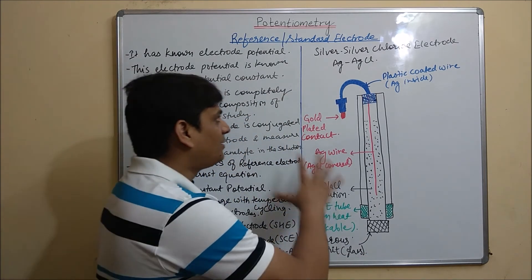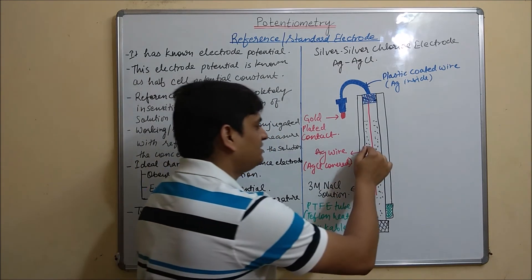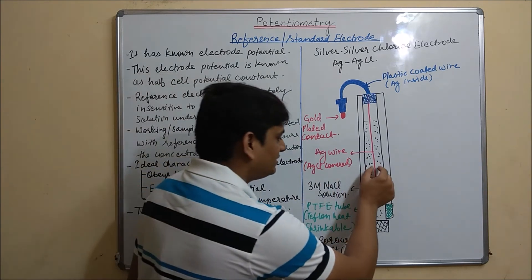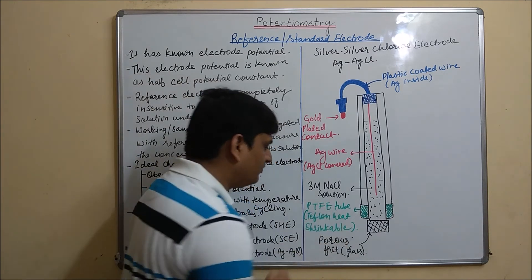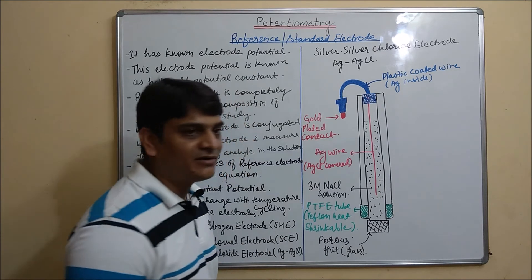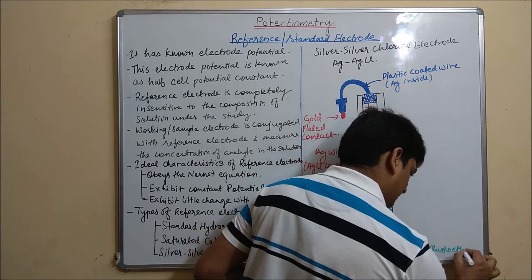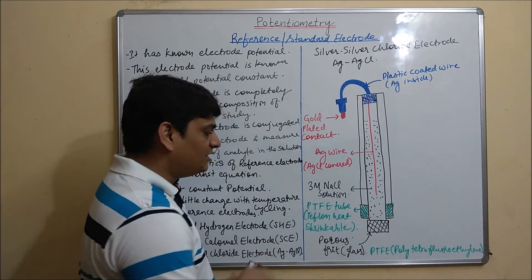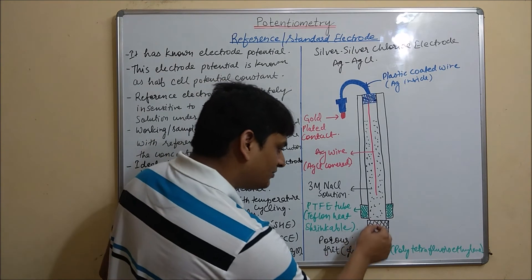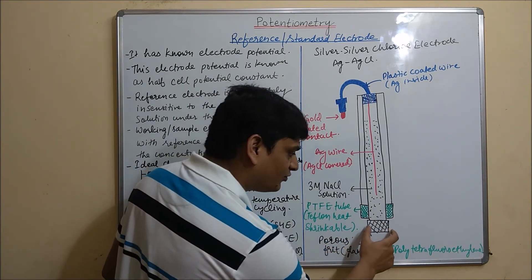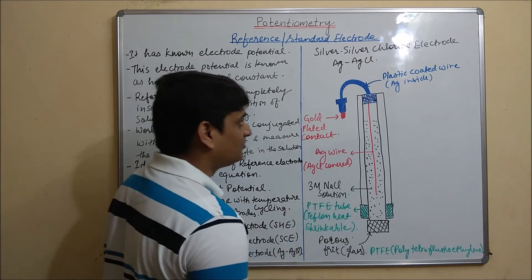This is the block diagram of the silver-silver chloride electrode. Here, one silver (Ag) wire is present, and this Ag wire is coated with AgCl. A 3 molar NaCl solution is filled in this electrode, and PTFE tubing is used. PTFE stands for polytetrafluoroethylene, also known as Teflon. The Teflon tubing is shrinkable with heat and is attached with a porous frit, that is porous glass, for dipping in the electrolyte solution. This is the complete setup of the silver-silver chloride electrode.